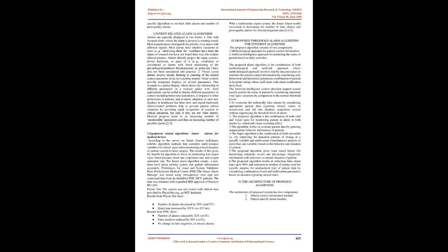Equipment-related algorithms, smart alarms for medical devices. According to the survey, smart alarm techniques exhibit algorithm methods that consider multi-instance variables for critical signs when monitoring the critical situation of patients recovering from heart surgery. The results give the benefit for the algorithm to focus on monitoring four major signs: blood pressure, heart rate, respiration rate, and oxygen saturation rate. The smart alarm algorithm creates a new, 3-level alarm priority system that gathers information accurately. Preferences for visual and system validation.